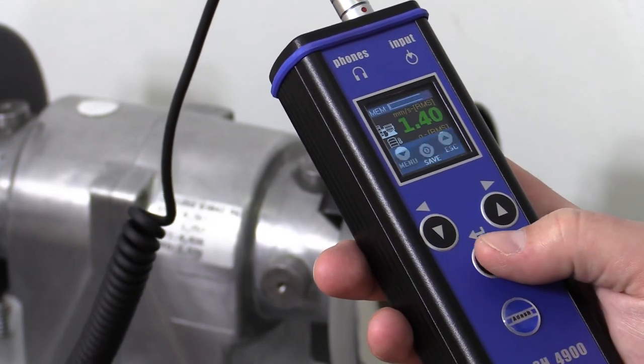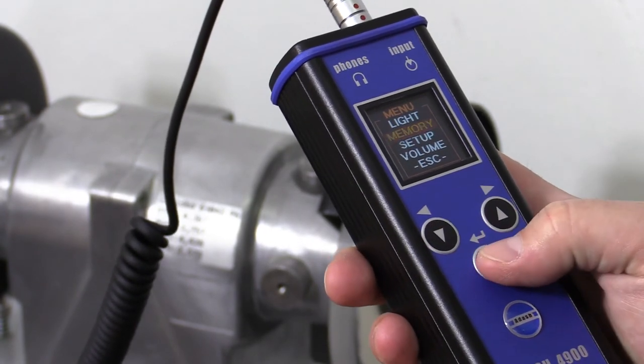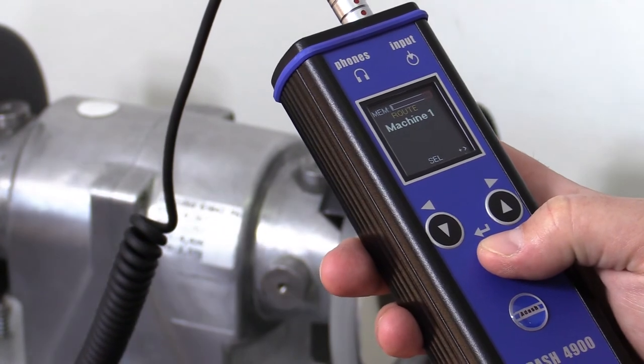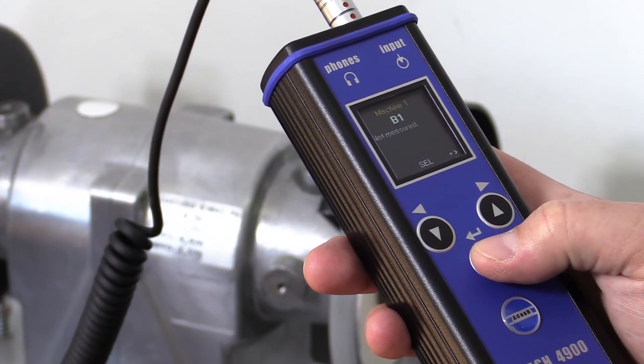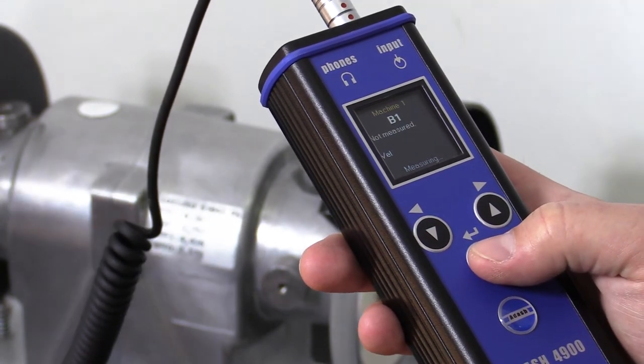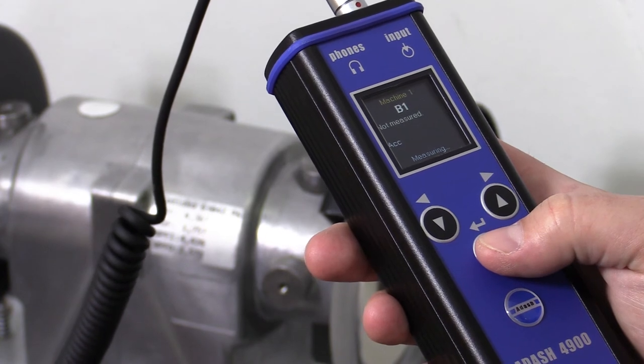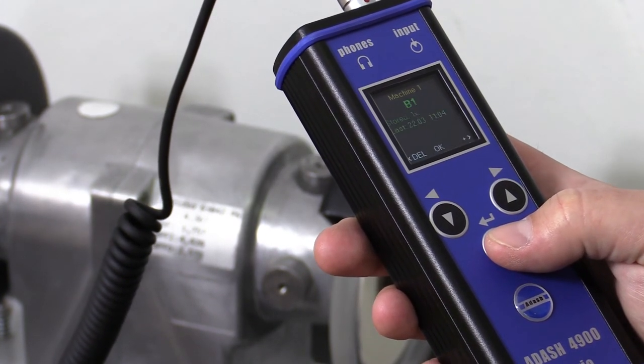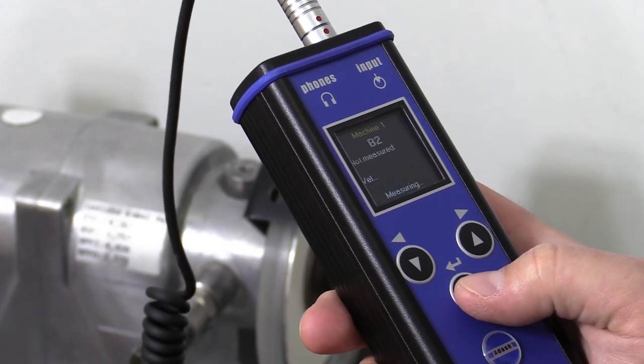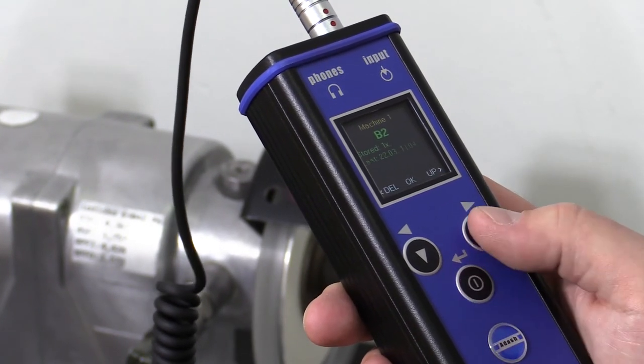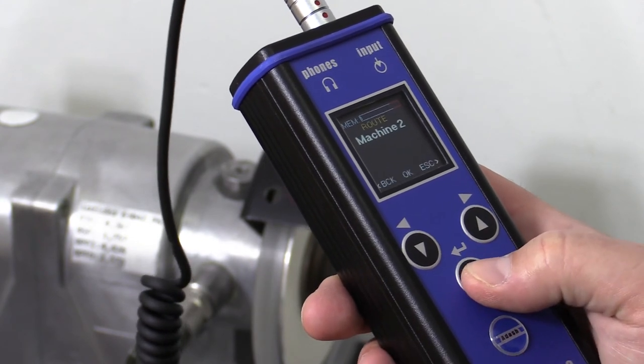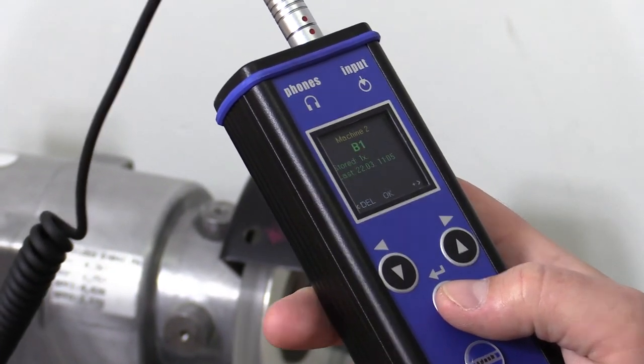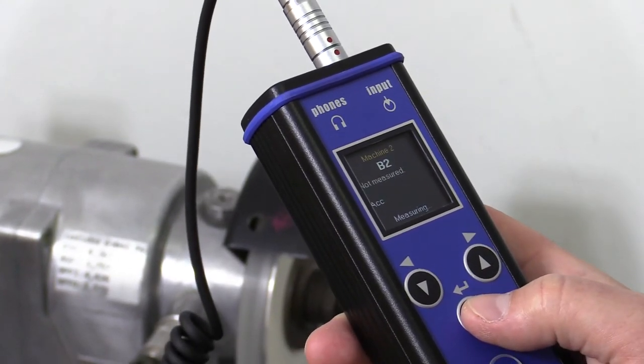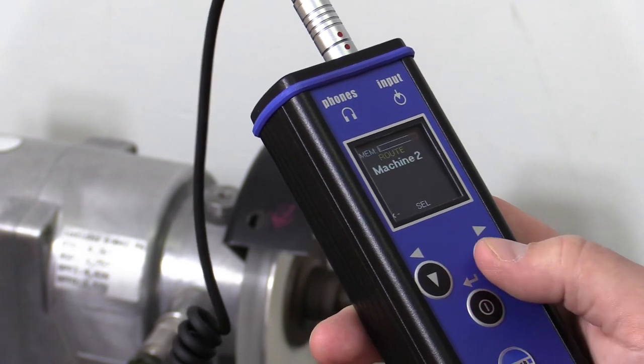Now we will perform measurement. I go to Menu, Memory, Route. Select Machine 1, confirm by OK, select B1 and press Measure. After successful measurement, the B1 point turns to green. I will go to B2 and measure B2 as well. Now I press up, go to Machine 2, and I will measure B1 and B2. Now press up, save and escape.